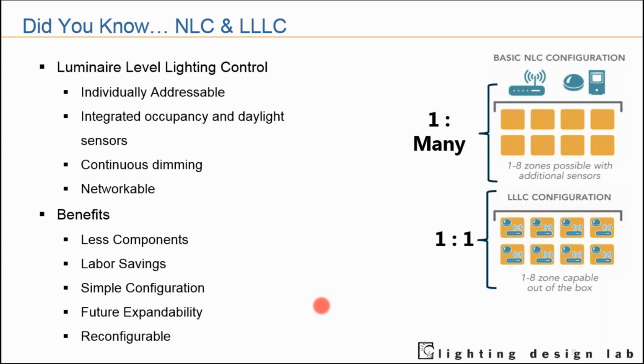Good way for us to visually see this is the one-to-one or the one-to-many approach and definition. We talk about, hey, a luminaire level lighting control configured space will have one daylight and occupancy sensor per each fixture. So one sensor per fixture, one load controller per fixture. That is that relationship. When we're talking about your typical zone grouping network lighting control system, we're talking one set of sensors, one daylight sensor, one motion sensor for many fixtures. They govern many fixtures.